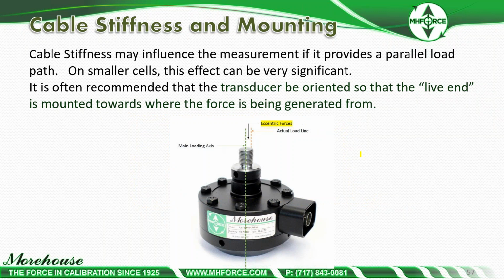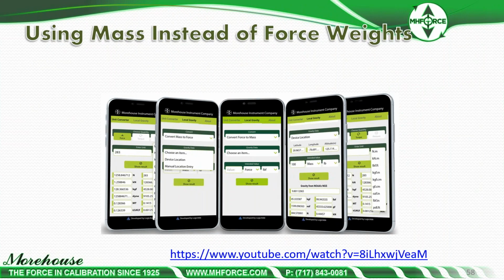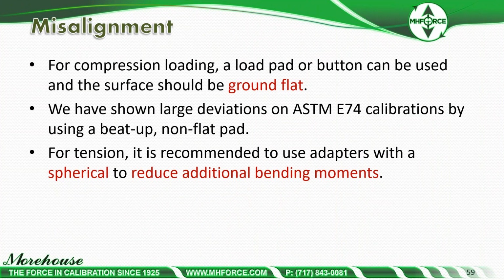So just something to be cognizant of: using mass instead of force weights, we covered that a bit earlier on what to do with that. Misalignment: for compression loading, a load pad or button can be used and the surfaces should be ground flat. We have shown large deviations on ASTM E74 calibrations by using a beat-up, non-flat pad. For tension, it is recommended to use adapters with spherical seats to reduce additional bending moments.